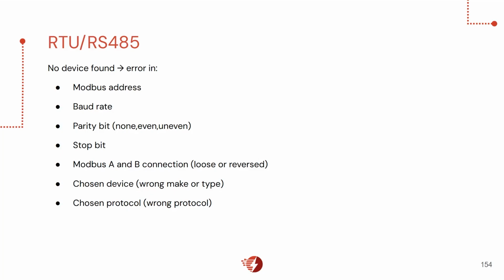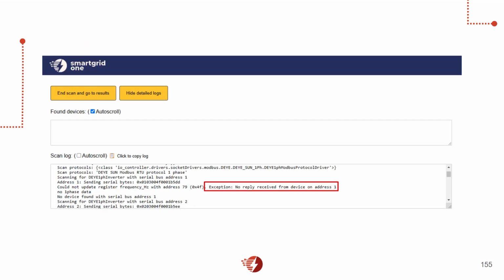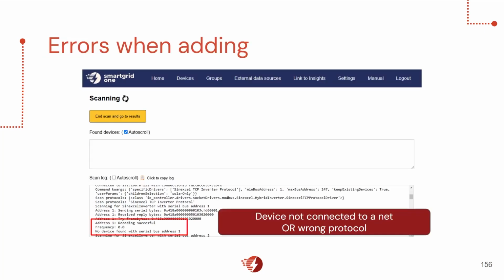For RS485, we have a few different errors. You could check the baud rate, the parity bits, even the stop bits. Even a physical connection can be made wrong, so do check the wires if they're not inversed. And again, the device and protocol can also be wrongly chosen. As you can see here, this means that the device is not connected at all, or you're using the wrong protocol.